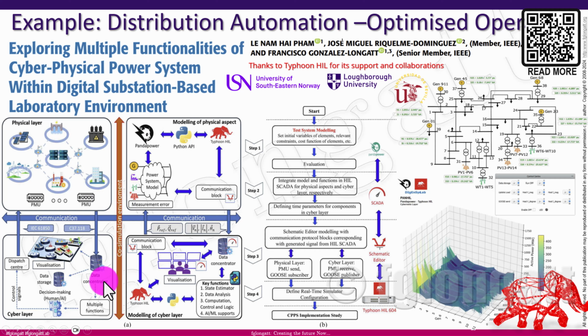These data streams are sent to the cyber layer, where we run an optimization algorithm. If there is a mismatch between generation and demand, the algorithm redispatches the generation and sends signals back to the physical layer to perform the redispatch. We use the industrial protocol IEC 61850 as the mechanism to close the loop, and in this case we can reach an optimized operation.